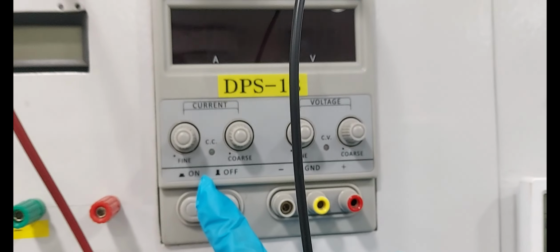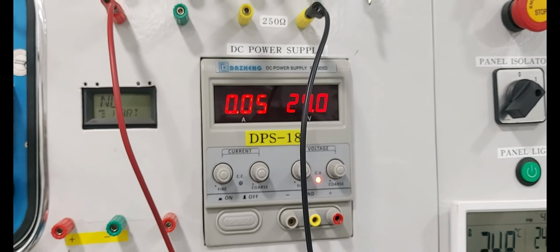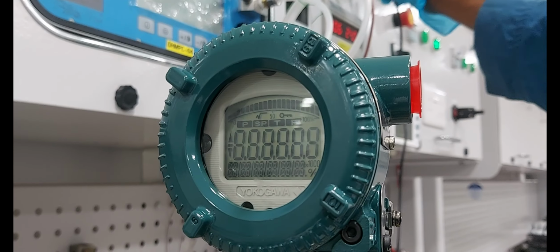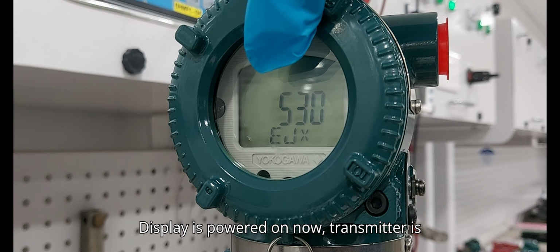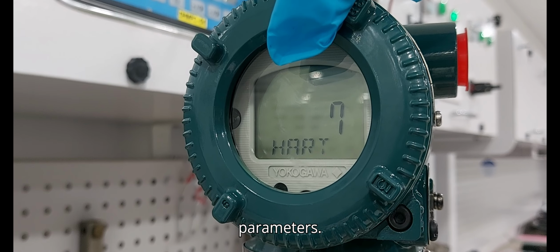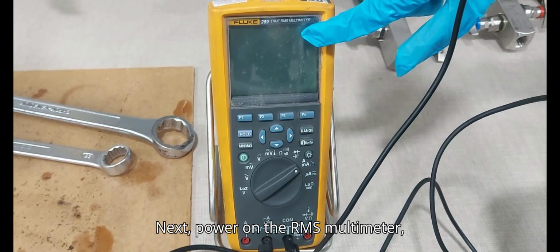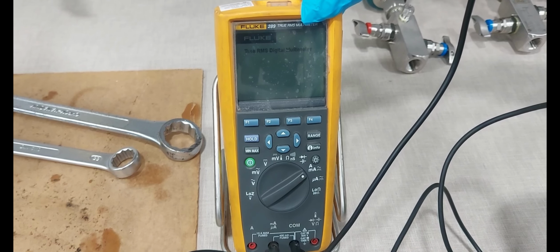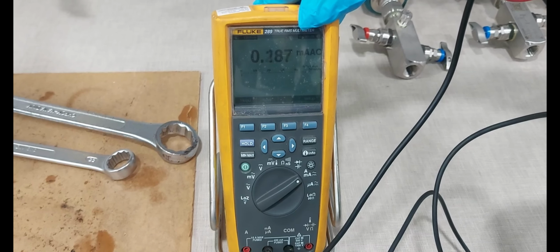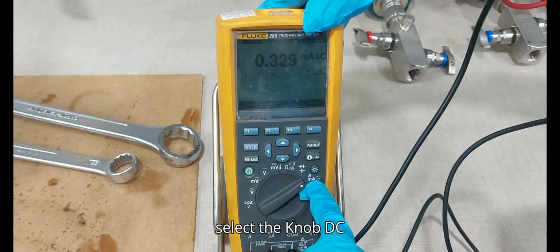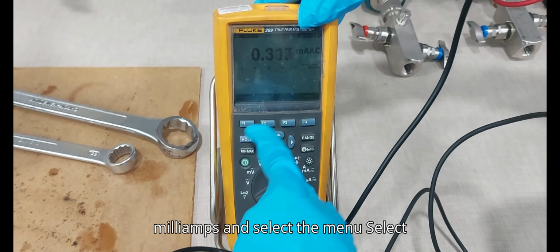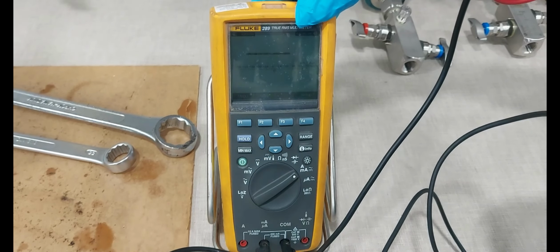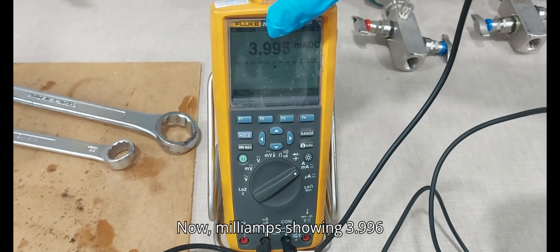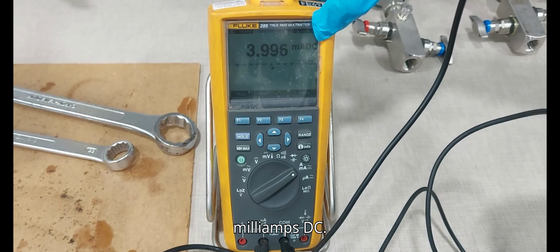Next, power on the 24 volt supply. The display is powered on now. The transmitter is powered on, and the display shows all parameters. Next, power on the RMS multimeter. Select the knob DC milliamps and select the menu DC. Now the multimeter shows 3.996 milliamps DC.